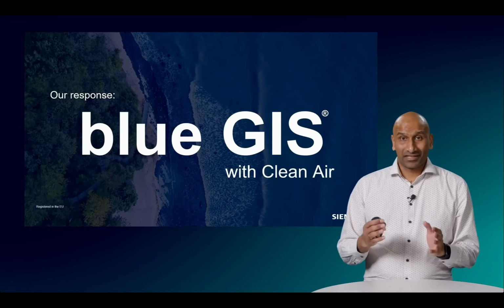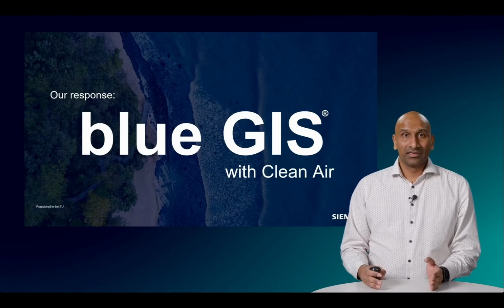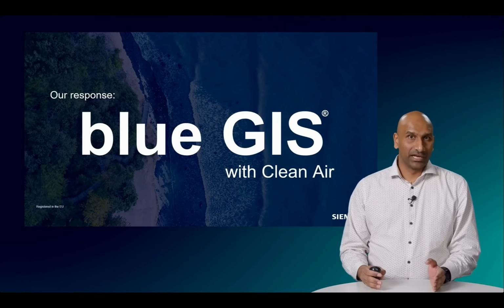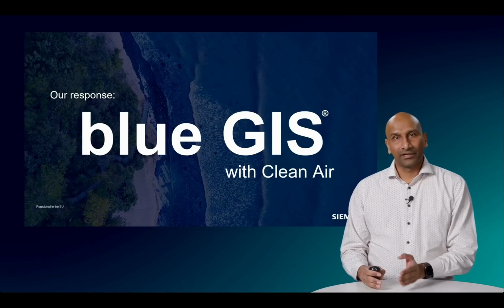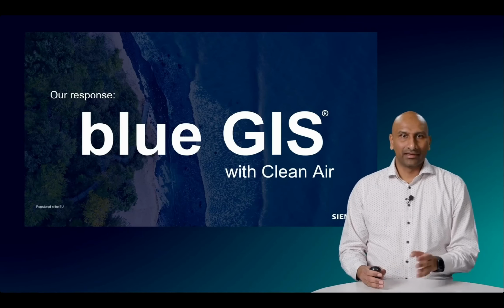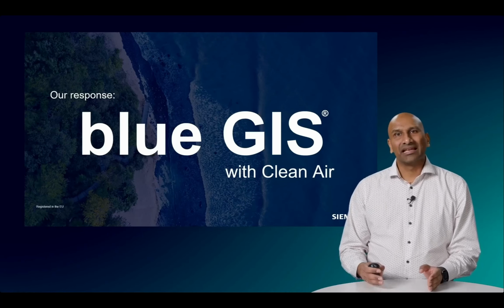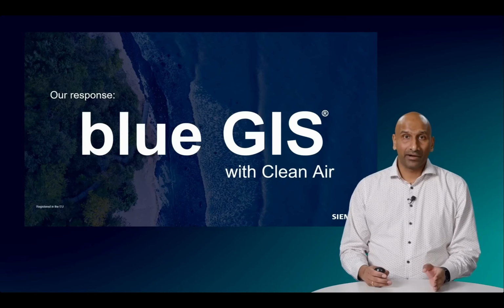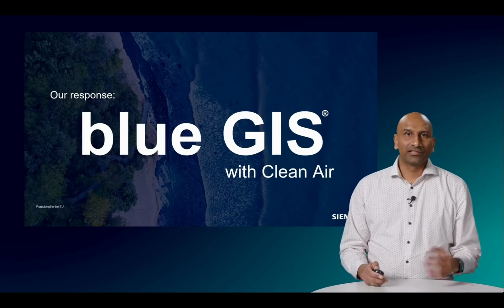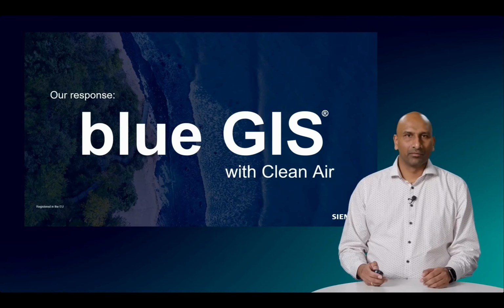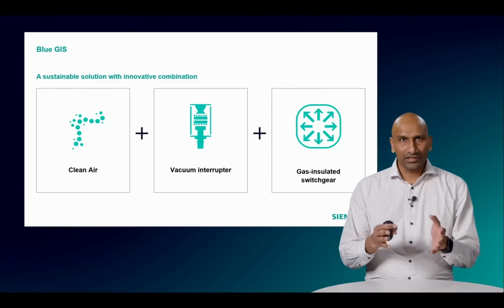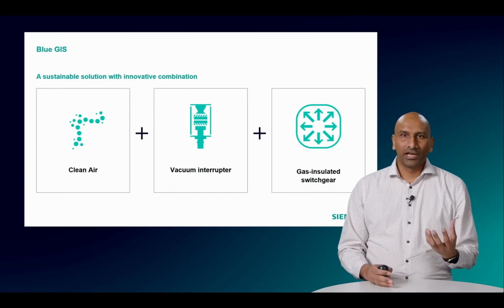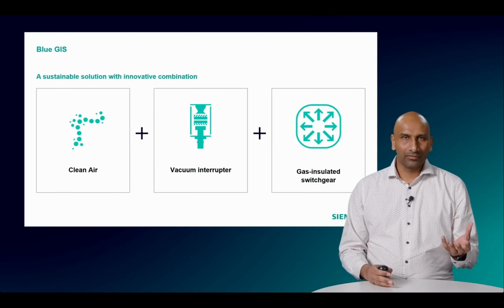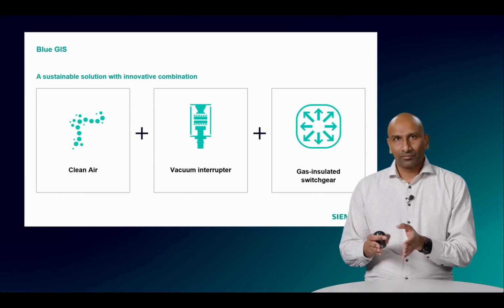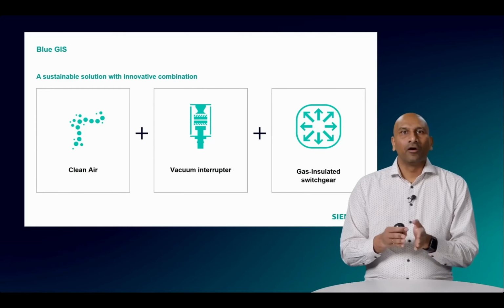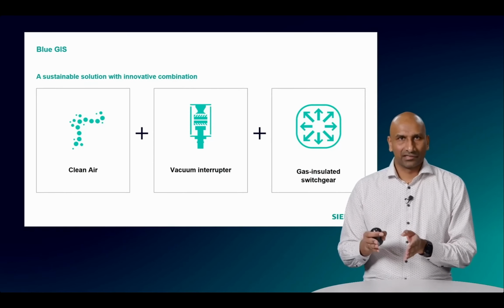To address the evolving needs of energy distribution, Siemens has developed BlueGIS, an innovative F-gas-free gas-insulated switchgear. This technology replaces traditional SF6 insulation with clean air, maintaining high performance while significantly reducing environmental impact. BlueGIS combines clean air as an insulating medium, a vacuum interrupter for current interruption, and all the features of a traditional gas-insulated switchgear.